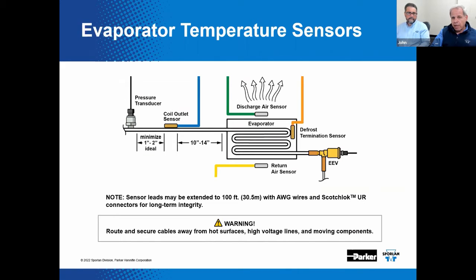We're specifying an 18 gauge recommendation for extensions, while the standard sensor wire is anywhere from 22 to 24, and the transducer 22 AWG. What AWG? What is that, John? American wire gauge. Okay, so that's a standard, right? Mm-hmm. Yeah. Now, and what about this color code thing? Does Sporlan ship these sensors with these color-coded wires? Yes, we do. Yeah, and so what do they all mean?